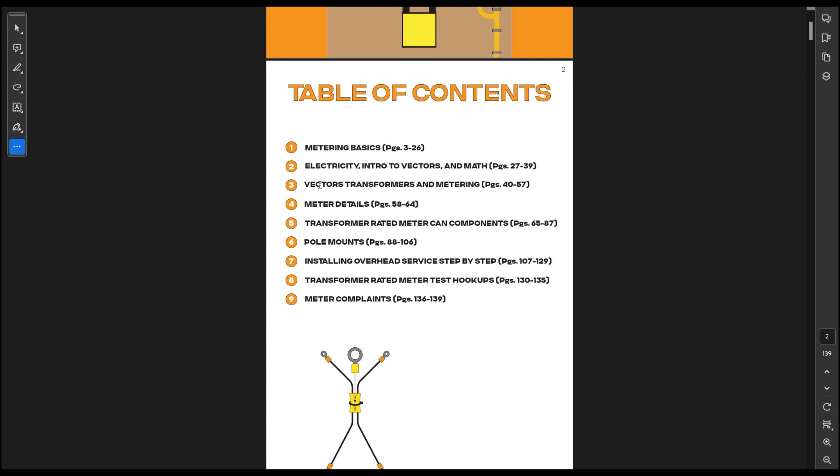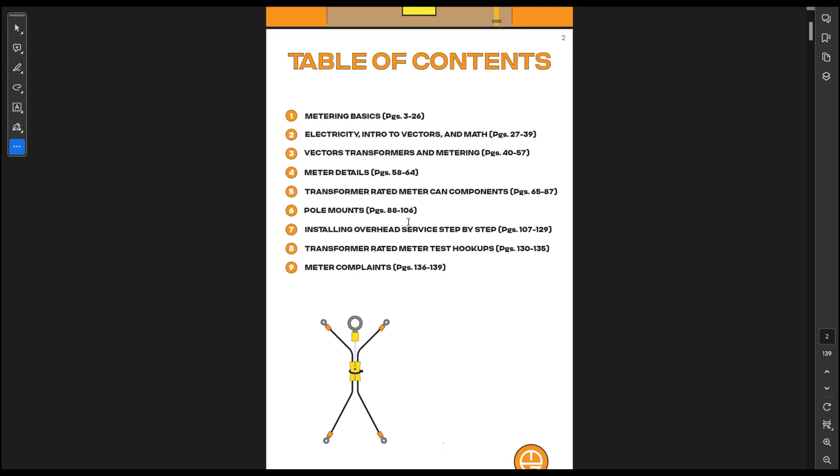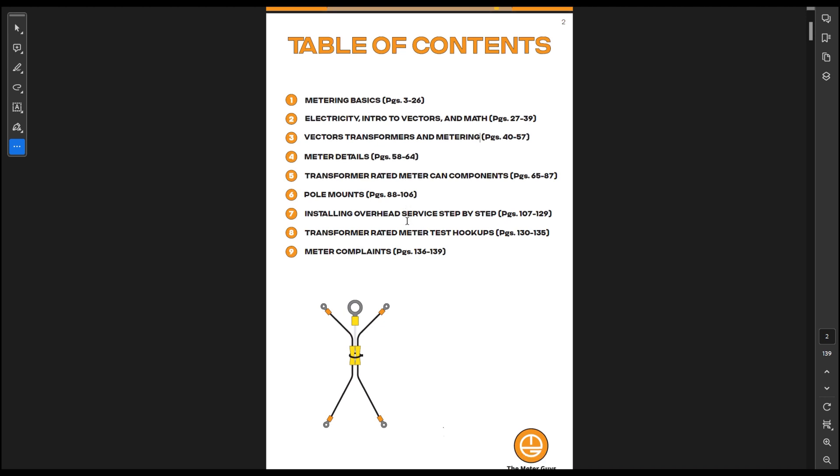The meter details, I kept that pretty basic. It goes over how we use solar and how we use time of use and normal meter displays and alternate meter displays. Transformer-rated meter can components, that is more just showing you what's inside the transformer-rated meters and what can shock you, what can't shock you. I go over a lot of the test switch and show the anatomy of it and how it all works.